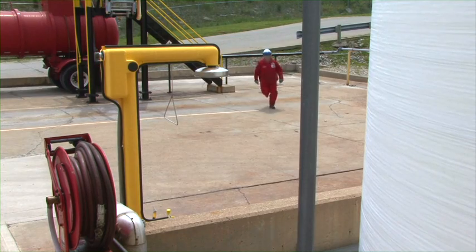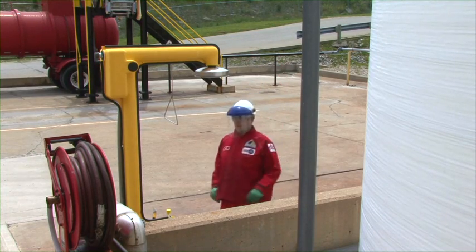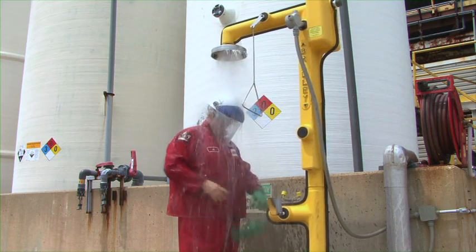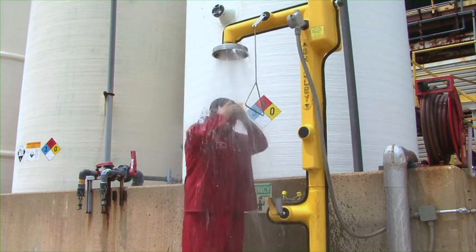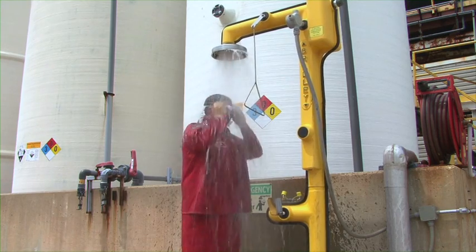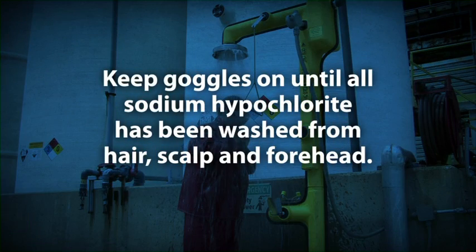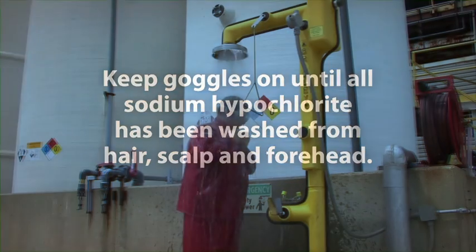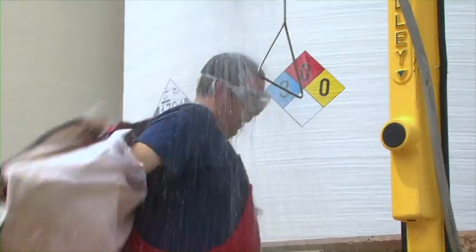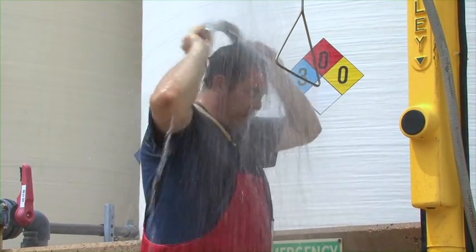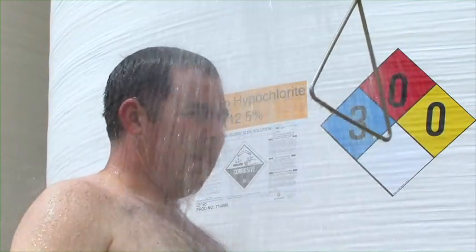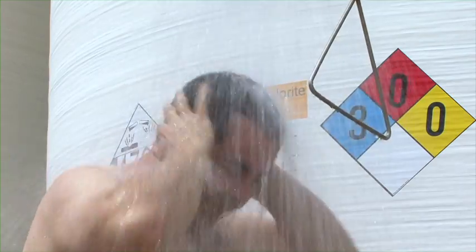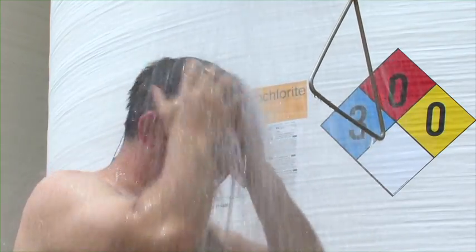If your skin, hair, or even clothing has been exposed to sodium hypochlorite, quickly get into a safety shower. Keep your goggles on and hold them tightly to your face unless your eyes have also been exposed. Goggles prevent sodium hypochlorite that might be in the hair or on the scalp or forehead from washing into the eyes. Once you are certain all sodium hypochlorite has been washed from hair, face, and hands, remove the goggles and clothing. Washing away the chemical residue from your skin is much more important than modesty. Continue washing for at least 15 minutes.